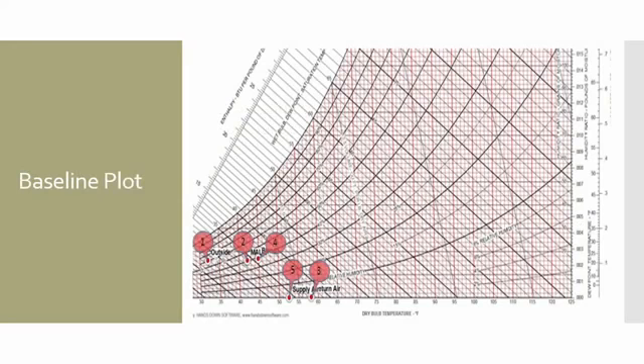Outside air measured at 32 degrees Fahrenheit with a relative humidity of 61%. Output of MAU2 was 42.1 degrees Fahrenheit. The return air going into DHU9 at that time was measured at 58.2 degrees Fahrenheit at negative 45.4 degrees Fahrenheit dew point. The blended air temperature moving through DHU9 was measured at 45 degrees Fahrenheit. And the measured supply air going into the room out of DHU9 was 52.5 degrees Fahrenheit with a dew point temperature of negative 67.5 degrees Fahrenheit.